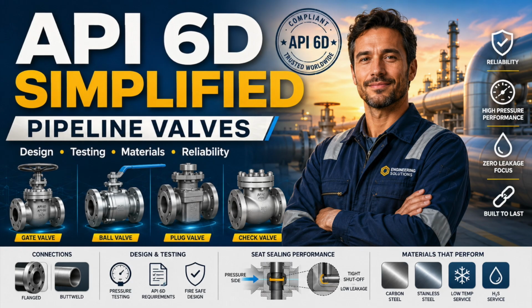Pressure class creates another false sense of security. A valve marked Class 600 is not automatically suitable for every Class 600 application. Pressure and temperature are connected. Material capability matters. Seal capability matters. Transient pressure matters. Minimum temperature matters. Depressurization matters. Fluid composition matters. A metallic body may tolerate the design condition while the non-metallic seat, seal, or packing does not. You therefore need to look beyond nominal pressure class.